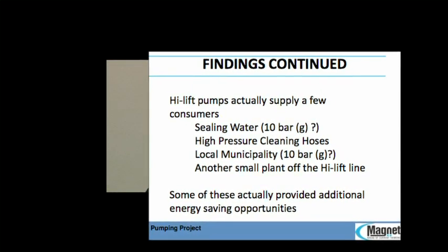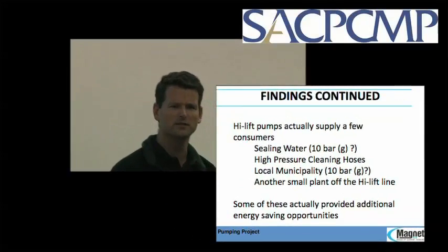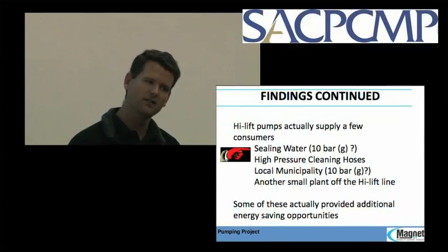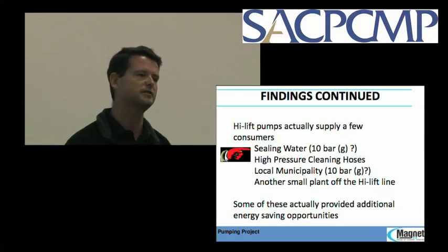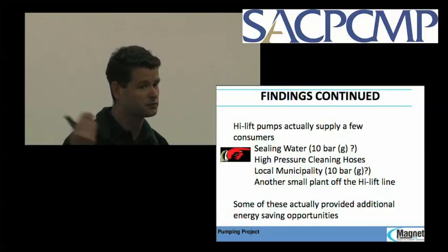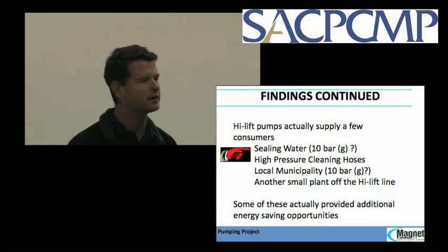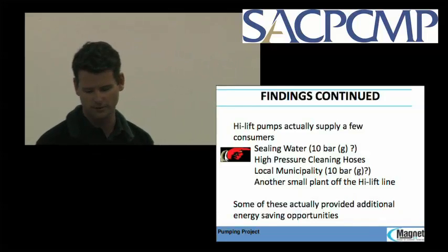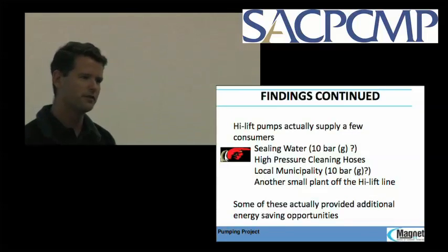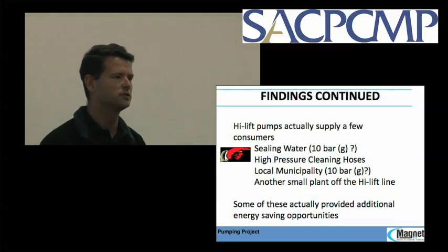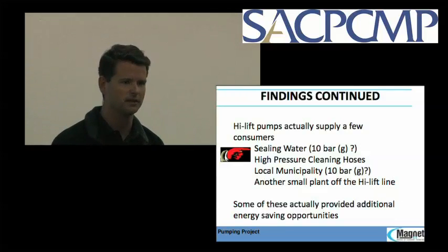After a while in the plant, we started talking, and I suddenly realized, well, wait a minute, where's the sealing water pump? Actually, the high lift pumps, which are supplying the mill at about 100 meter head to get up to the mill reservoir, were also supplying sealing water to all the pumps in the plant. So now they had 10 bar sealing water. First thing is that there's obviously an energy saving opportunity here, because you don't need 10 bar water for sealing.